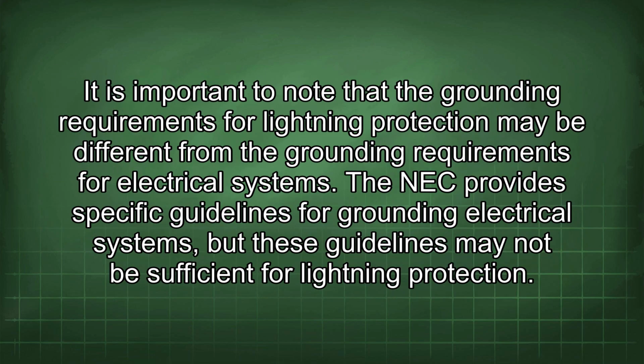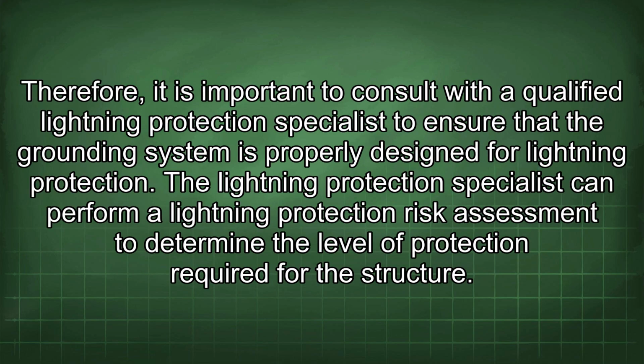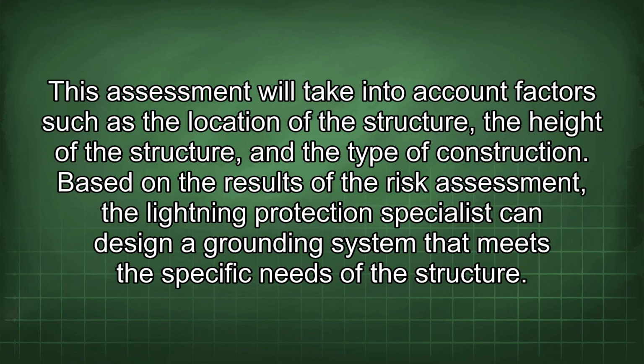It is important to note that the grounding requirements for lightning protection may be different from the grounding requirements for electrical systems. The NEC provides specific guidelines for grounding electrical systems, but these guidelines may not be sufficient for lightning protection. Therefore, it is important to consult with a qualified lightning protection specialist to ensure that the grounding system is properly designed for lightning protection. The lightning protection specialist can perform a lightning protection risk assessment to determine the level of protection required for the structure. This assessment will take into account factors such as the location of the structure, the height of the structure, and the type of construction.